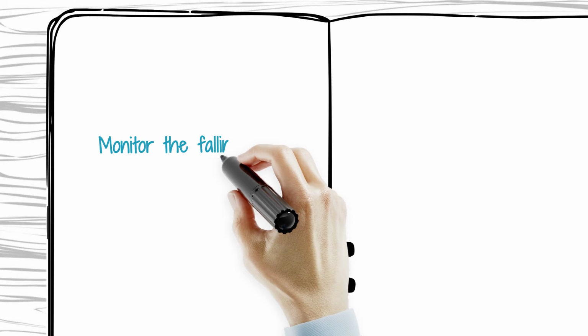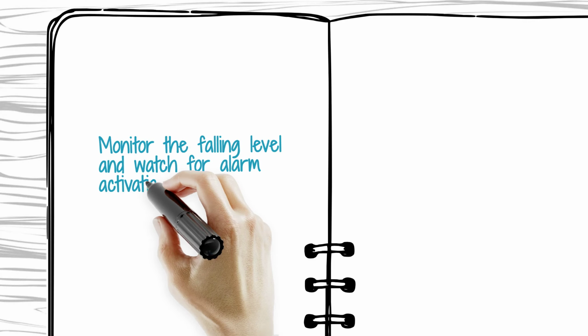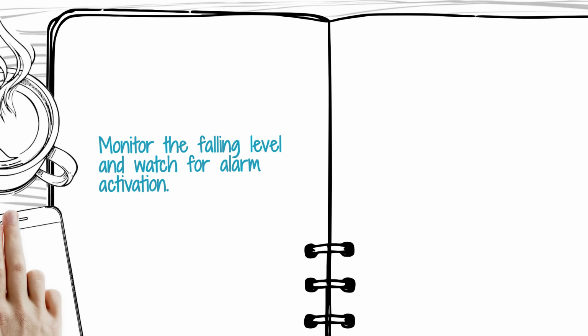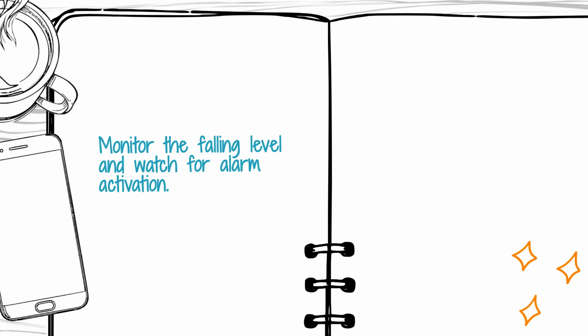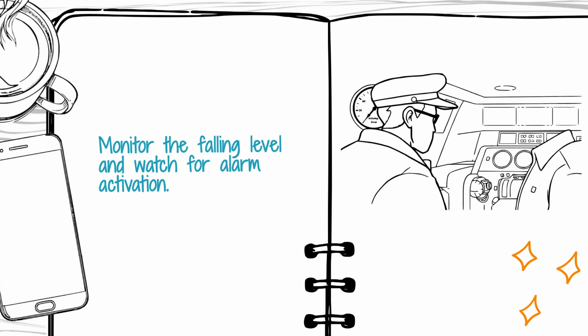Watch the gauge glass on the side of the chamber or monitor the milliamp signal from the transmitter as the level falls. The moment the water reaches the designated low-level mark, the alarm must trigger on the main engine room console.